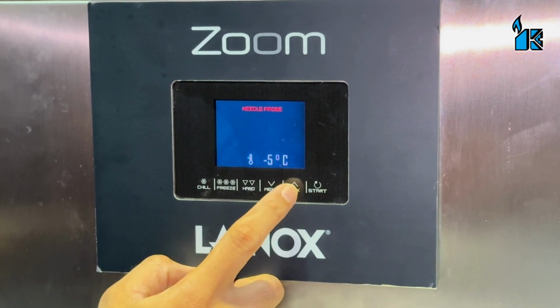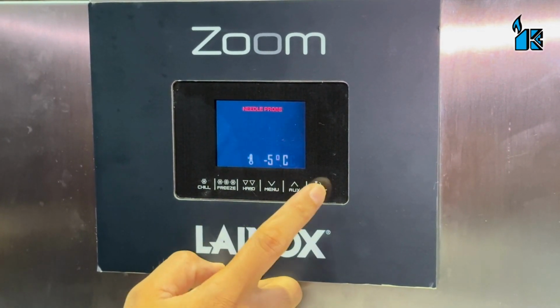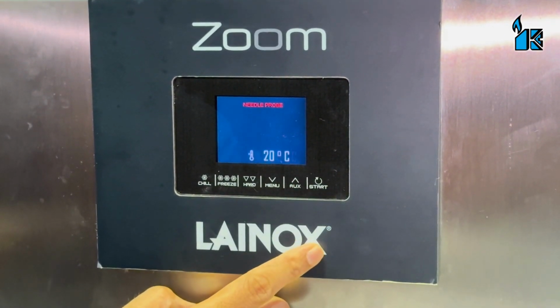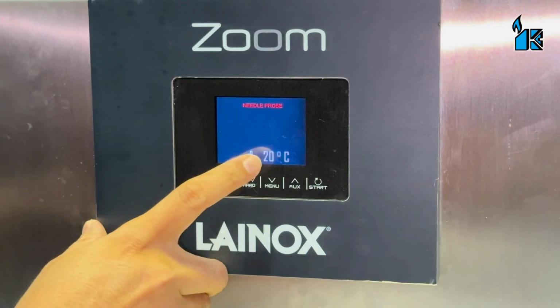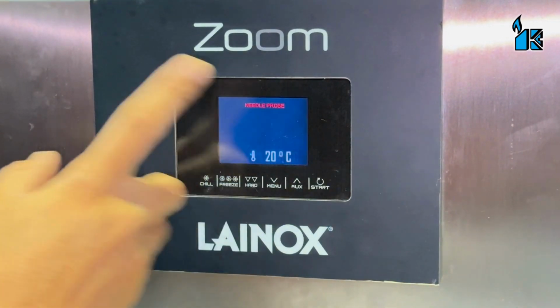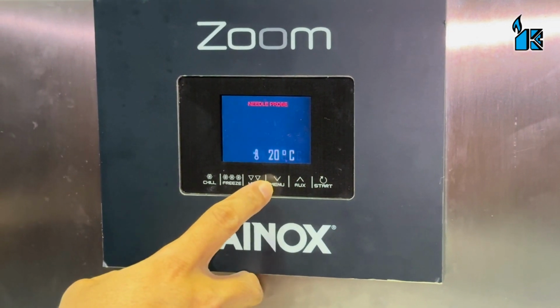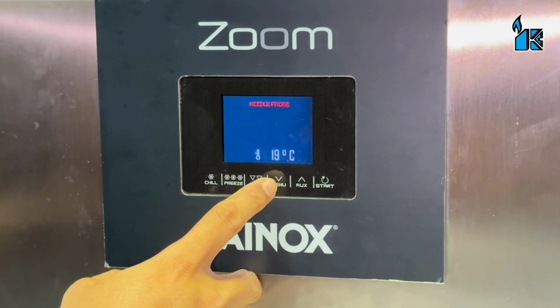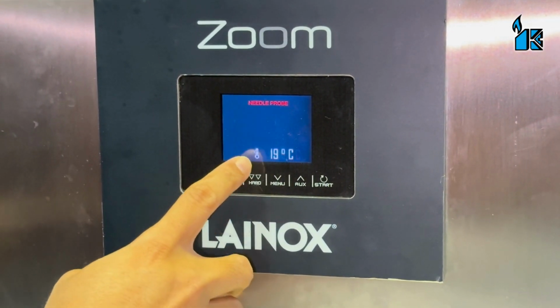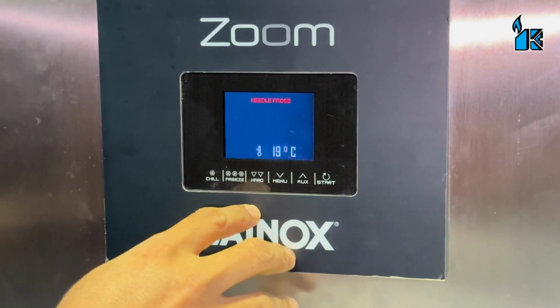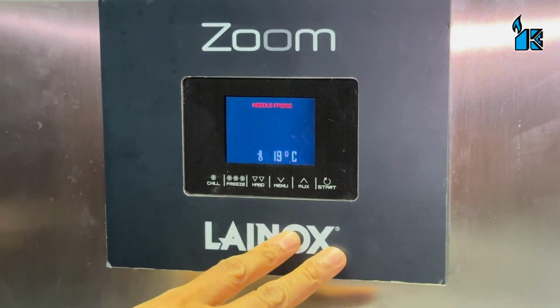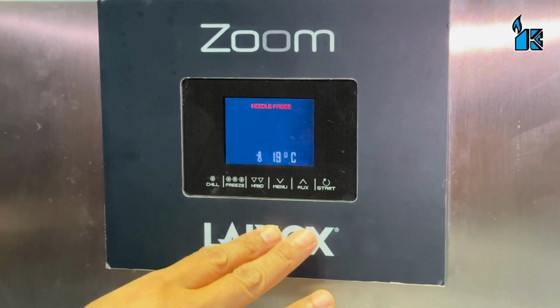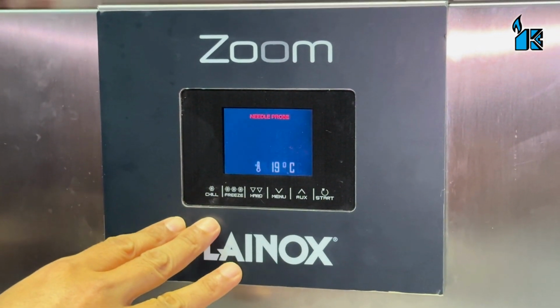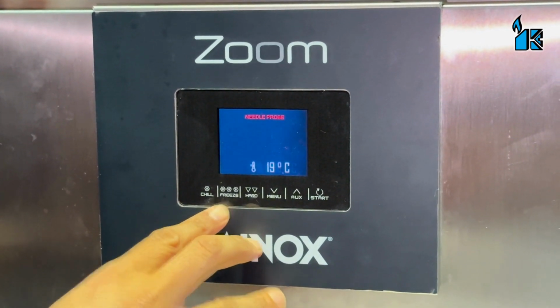Let's say I set to -5 and then I start the pre-cooling mode. Currently it shows 20 degrees inside the chamber. So the machine does pre-cooling until the chamber temperature reaches -5 and it will stop. Then after that you can start your normal process with the chill or freezing.